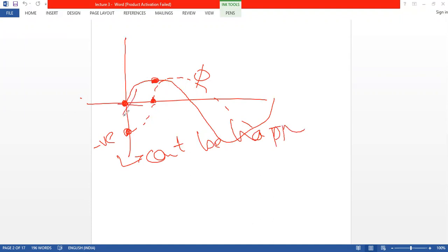So when the voltage is switched on, your transformer is switched on when the voltage is crossing the 0 point, the flux cannot be negative. So what will happen when it reaches the peak and when it is started here, the flux will start from the initial point and it will reach double the value. To cover this point, it will go from negative to this positive value here. So it will reach double. You can say this is called the doubling effect, 2 phi m. This is called the doubling effect.